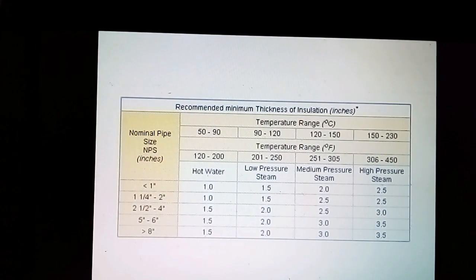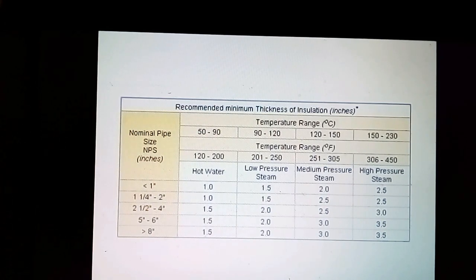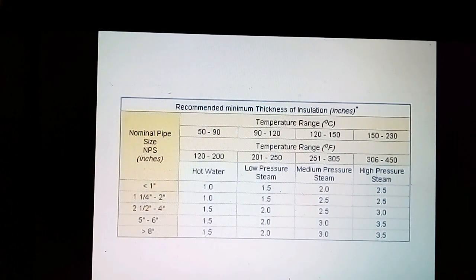The table gives the recommended minimum thickness of insulation in inches. It is for a temperature range of 50 to 230 degrees centigrade, or 120 to 450 degrees Fahrenheit. The ranges of temperature correspond to hot water, low-pressure steam, medium-pressure steam, and high-pressure steam. The nominal pipe size varies from half inch to 8 inches and more.